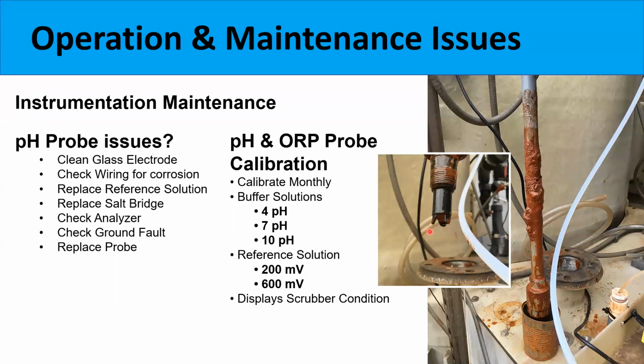Those electrodes are very sensitive. They contain a salt bridge within them and require very frequent calibration. Typically monthly is what we recommend, with buffer solutions of 4, 7, and 10 pH. Those probes, if that sump and that scrubber is just not maintained with good fresh water and a good blowdown, then those probes can start to get built up on them.